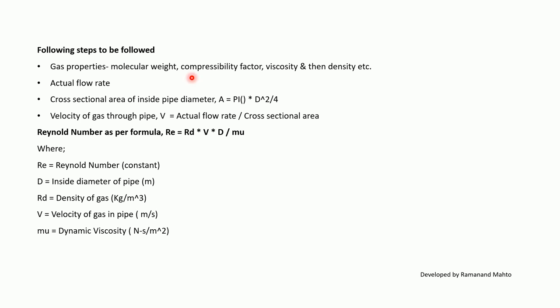Then calculate the actual flow rate. Next, calculate the cross-sectional area of the inside pipe diameter: A = π × D² / 4. Then calculate the velocity of gas through the pipe: V = actual flow rate / cross-sectional area.